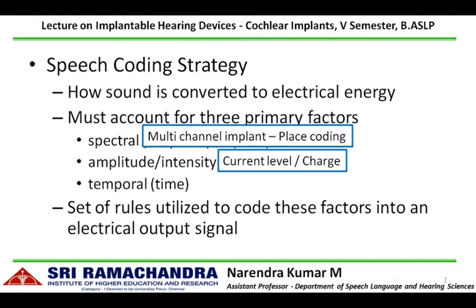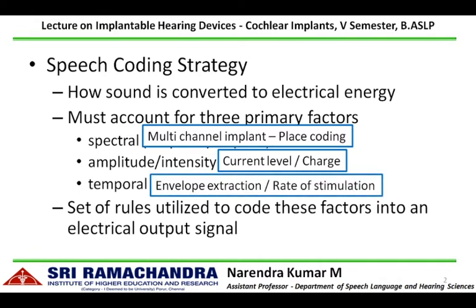The amplitude information is controlled by the charge level — the electrical energy level delivered to each electrode contact area. If the electrode contact represents a soft signal, lower charge is delivered; if it is a loud, high-intensity signal, the charge is going to be high. The temporal information is extracted from envelope extraction, showing how the signal varies across time.